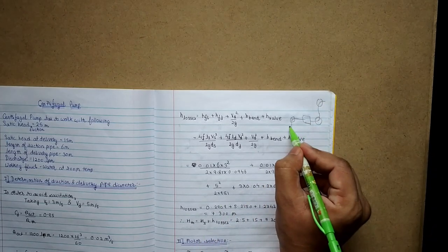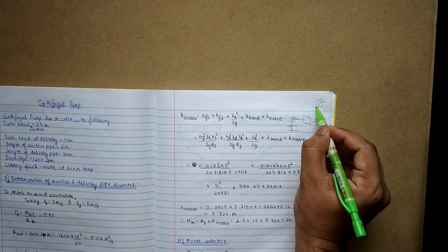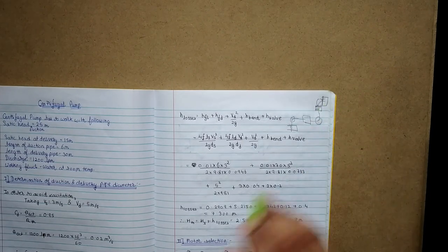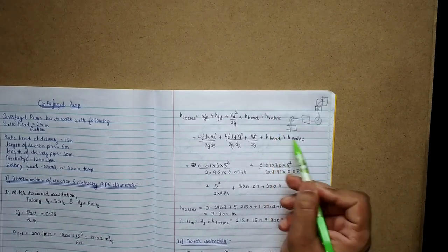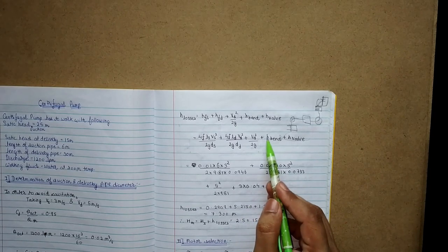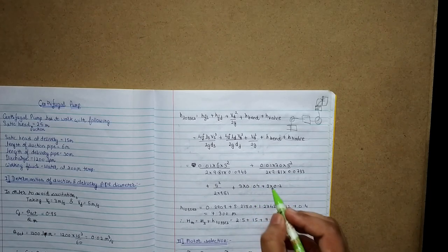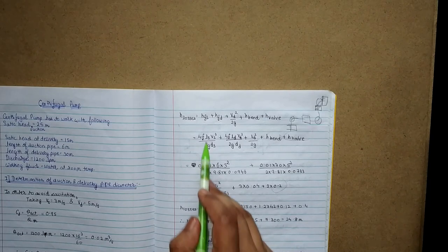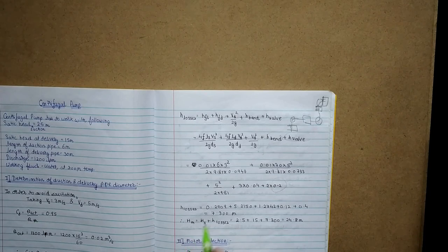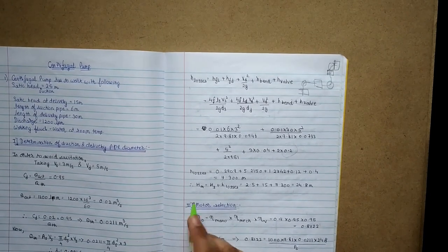We consider three bends and two valves — one suction valve and one delivery valve. The loss at each bend is taken as 0.04 and the loss at each valve is taken as 0.2. Putting all the required values into the formula, we get the value of total head losses as 7.300 meters.